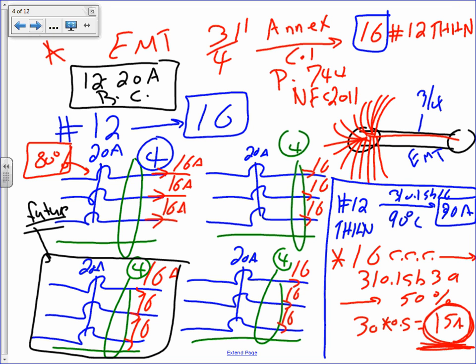One more time. Look at this circuit here. I have 3 20 amp circuits, right? 3 20 amp circuits tied together. Each one of them can only provide 16 amps because it's continuous. So I can have 3 grouped together with a neutral, 3 grouped together with neutral, 3 grouped together with neutral, 3 grouped together with neutral. Can I have thumbs up? We understand what you're doing, Chad? Yes? No? Okay.